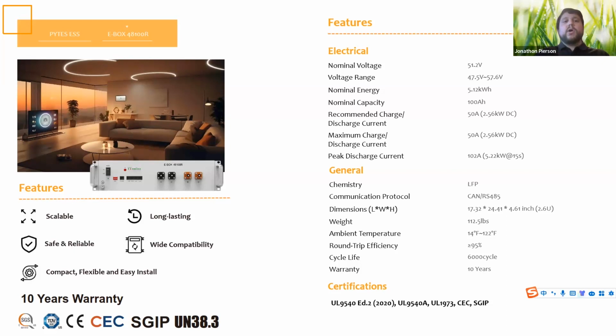I want you to understand the warranty is 10 years, which is phenomenal, with 6,000 cycles at 90% depth of discharge. But what if you size a Pytes lithium iron phosphate battery system at 80% depth of discharge? In other words, you oversize your battery bank 20% larger than your max daily kilowatt hours needed from storage.